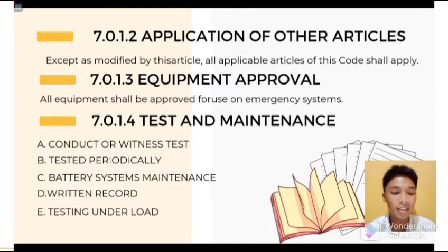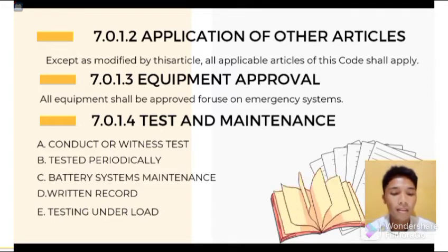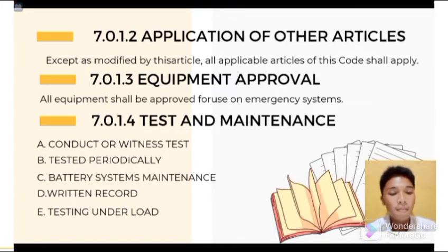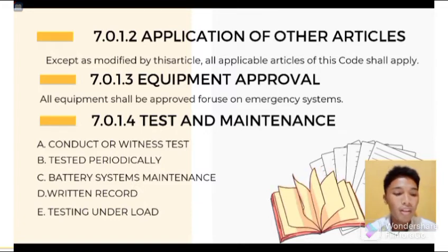Application of other articles. Except as modified by this article, all applicable articles of this code shall apply. Equipment approval. All equipment shall be approved for use on emergency systems. Test and maintenance. Letter A, conduct or witness tests. The authority having jurisdiction shall conduct or witness a test of the complete system upon installation and periodically afterward. Letter B, tested periodically. The system shall be tested periodically on a schedule acceptable to the authority having jurisdiction to ensure that the systems are maintained in proper operating condition.